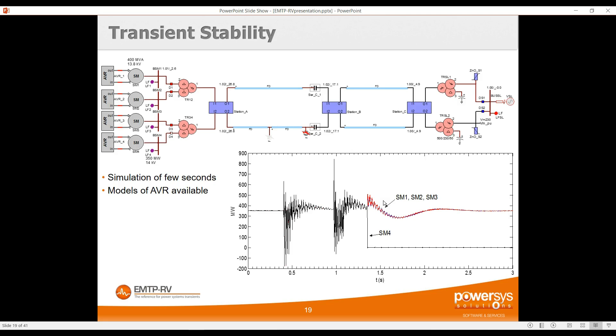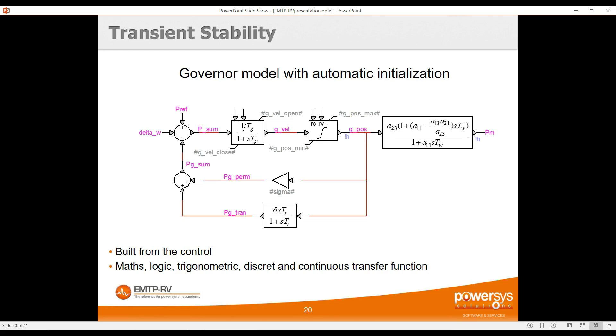Transient stability is also a very typical EMTP case study. Here we have long series-compensated lines, generation units, and a network equivalent. The AVR voltage regulator control is built in, and we simulate several reclosing events, disconnect a machine, and observe the dynamics reaching a new steady state — verifying network stability. The governor is built using the EMTP control library, which includes transfer functions, logic, trigonometry, etc., allowing construction of all kinds of control strategies.